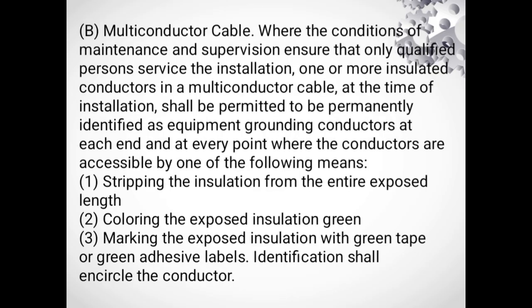B. Multiconductor cable, where the conditions of maintenance and supervision ensure that only qualified persons service the installation, one or more insulated conductors in a multiconductor cable, at the time of installation, shall be permitted to be permanently identified as equipment grounding conductors at each end and at every point where the conductors are accessible by one of the following means. 1. Stripping the insulation from the entire exposed length. 2. Coloring the exposed insulation green. 3. Marking the exposed insulation with green tape or a green adhesive label. Identification shall encircle the conductor.